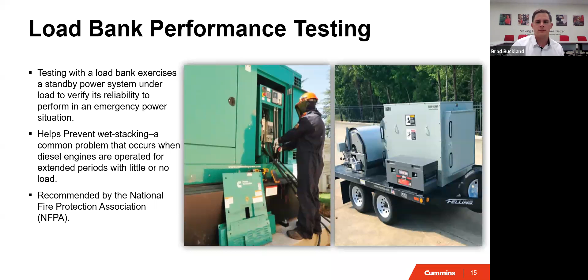We as a company, we operate and do planned maintenance on all different types of equipment. So this is actually a Caterpillar engine that we're working on here, and we're doing the load bank for this hospital. So they have a 4-hour requirement based on their Joint Commission standards, which is right here at the top. It says standard NFPA 110, which is the one we always operate off of, and then any additional ones. So hospitals every 3 years have to have this 4-hour load bank instead of a 2.